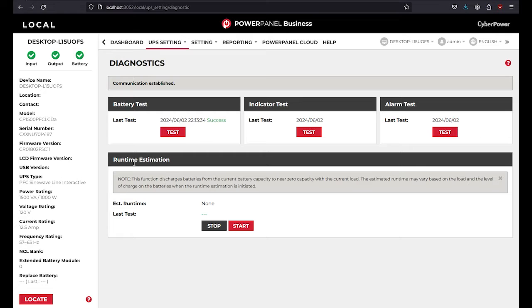Runtime estimation. Note, this function just discharges the batteries from current capacity down to near zero at the current load. The estimated runtime may vary based on the load and the charge level of the batteries when they run. So it literally just runs it all the way down. I wonder if it's just giving an estimate, or if it's actually going to calibrate the readout. Either way, that's cool, although kind of a risky feature to use, since lead acid batteries aren't meant to be fully discharged. It kills them quite quickly.